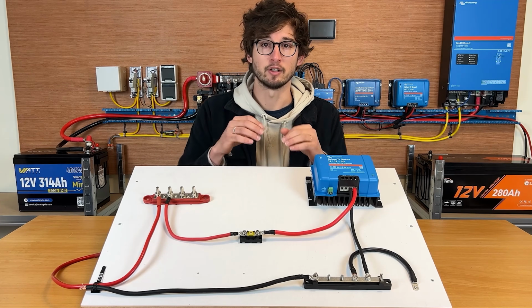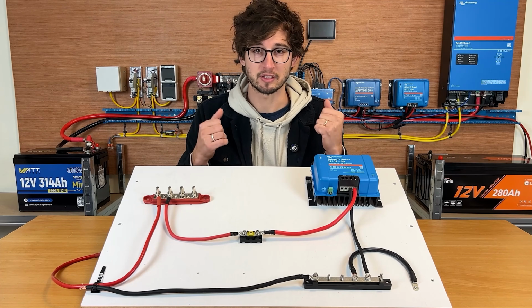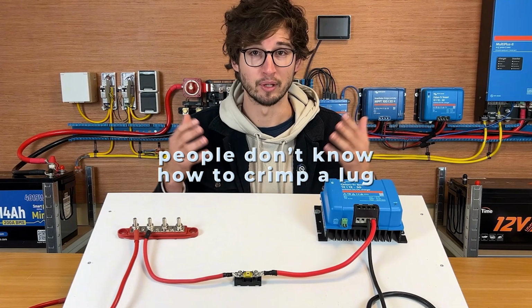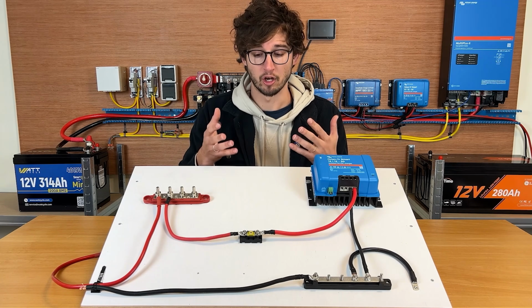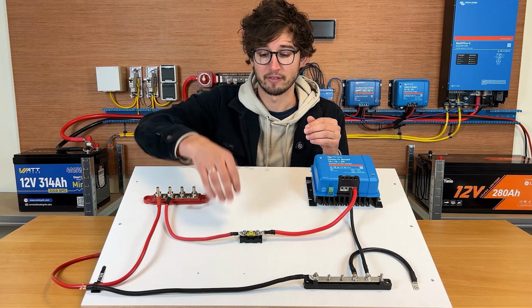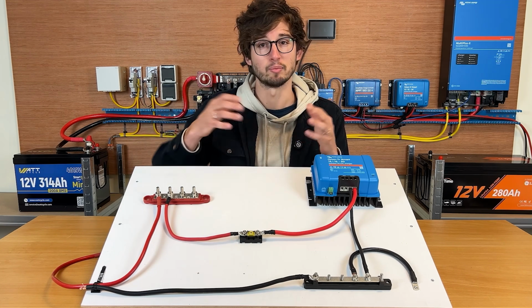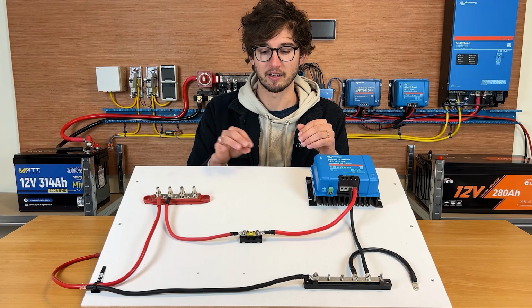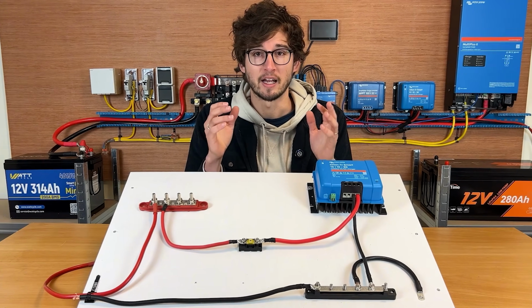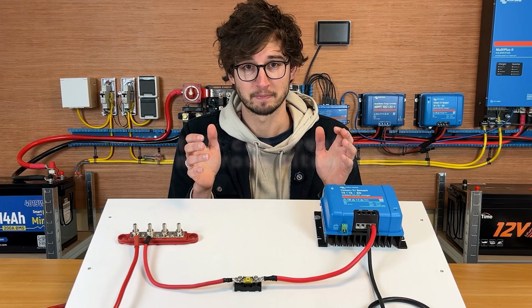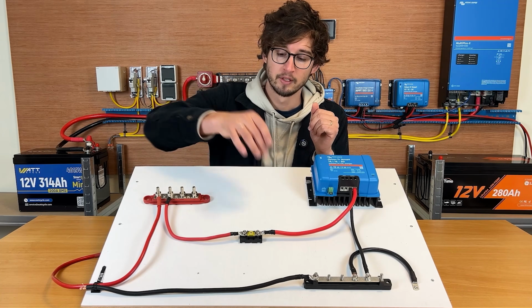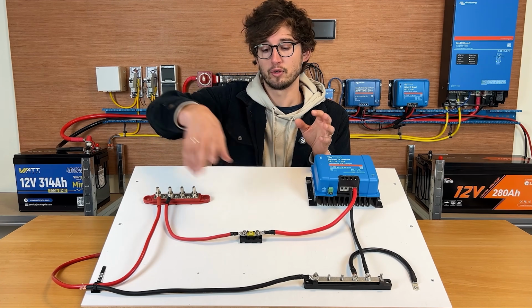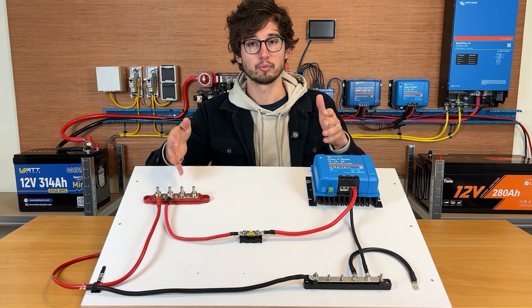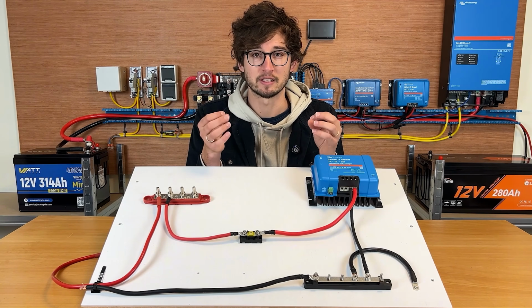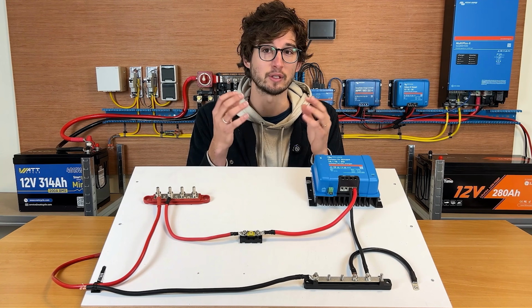At this point I often see people make the same mistake. People don't know how to crimp a lug. They use the wrong size lugs on the wires, or they buy very cheap lugs from Amazon, for example. They are very thin and don't conduct very well. This can create dangerous situations, because if you make a bad crimp, the energy cannot flow directly to or from your device, and it creates resistance, and that resistance creates heat.